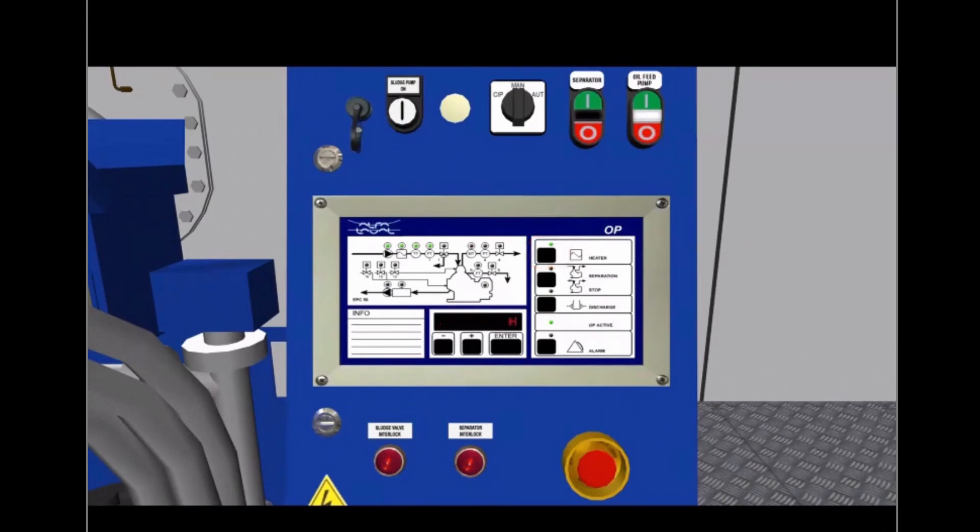Press the separation button to start the separation process. Before the separator can be started, a number of questions have to be answered. If no work has been carried out on the bowl, press the minus button. No calibration of the system is then required, and the start sequence begins.